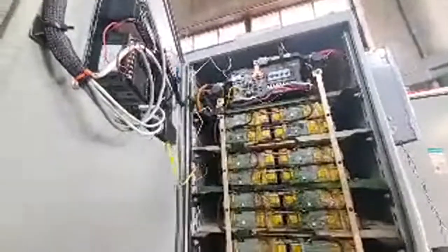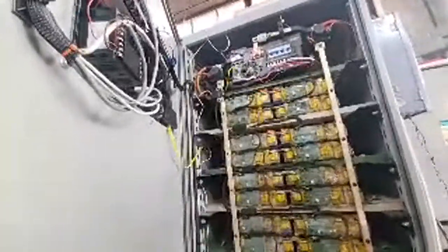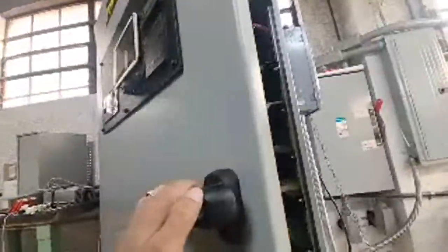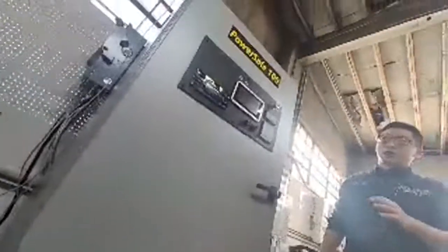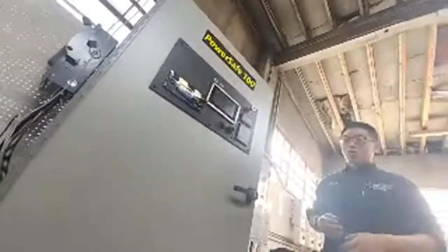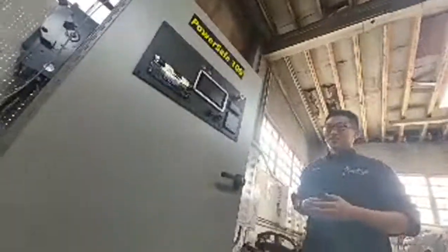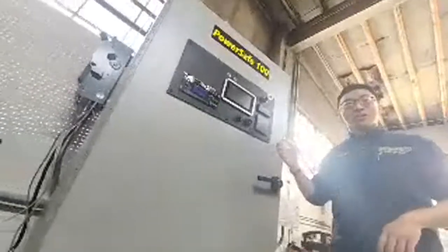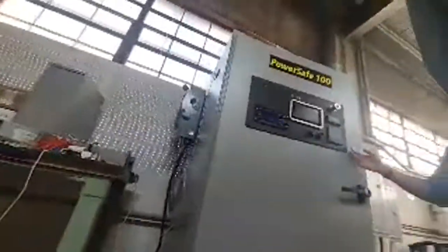So it can't handle the almost 30 kilowatts of solar in the summer — that's way too much. That's why we're using a 30 kilowatt inverter with the full pack, the Model 3 full pack. See, for the Model 3 full pack, even at maximum power, it's only like 70-80 amps. For this one, we'd go over like 300-400 amps.